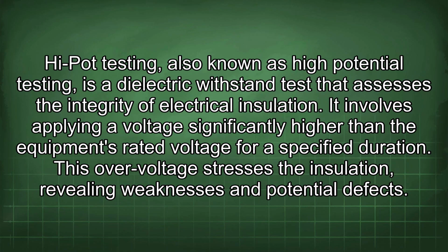High pot testing, also known as high potential testing, is a dielectric withstand test that assesses the integrity of electrical insulation. It involves applying a voltage significantly higher than the equipment's rated voltage for a specified duration. This overvoltage stresses the insulation, revealing weaknesses and potential defects.